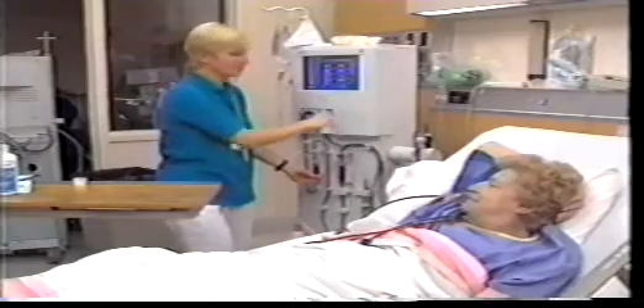Excess blood leakage may lead to patient shock. In the rare event of a leak, the catheter should be clamped immediately. Necessary remedial action must be taken prior to resuming dialysis. Do not over-tighten connectors, as the wear and tear over repeated use could degrade the connection integrity. With each hemodialysis, the patient's temperature is checked at the start and end of treatment. The catheter exit site is visually inspected for purulent drainage or erythema of the surrounding skin. Fever or evidence of an exit site infection is reported to the physician.